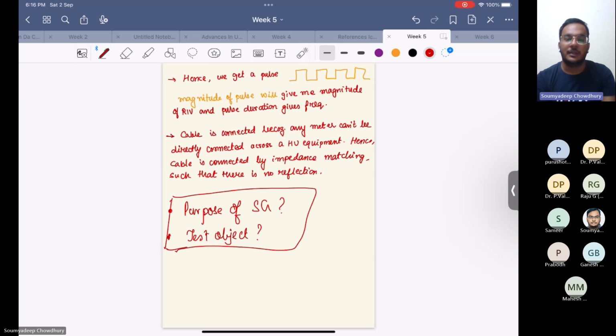This cable is connected with impedance matching so there is no reflection, because these high voltage, high frequency signals have an issue of reflection - we've seen the traveling wave phenomena. Any voltage or current signal travels as a wave, and if it sees any impedance mismatch at a junction, some part will be reflected and some part transmitted. So suppose there is one impedance, a junction here, and another impedance - this is what we consider.